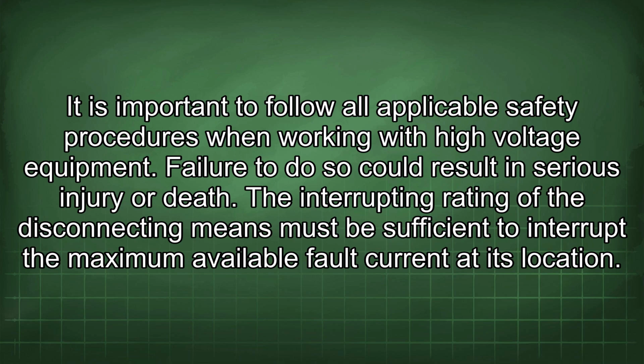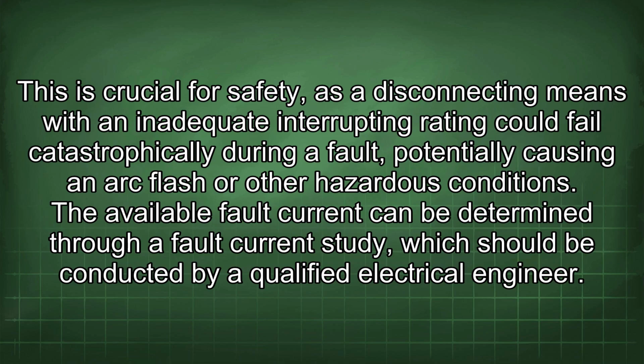The interrupting rating of the disconnecting means must be sufficient to interrupt the maximum available fault current at its location. This is crucial for safety, as a disconnecting means with an inadequate interrupting rating could fail catastrophically during a fault, potentially causing an arc flash or other hazardous conditions.